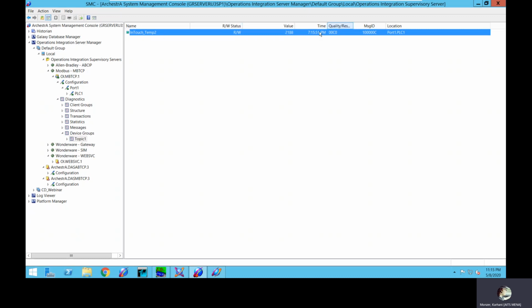If it's green and the value is frozen or you don't have a value, that means everything's fine, except there is something, maybe a firewall or something in the security, that doesn't allow you to read from the field. So look at your security, firewall or antivirus maybe.